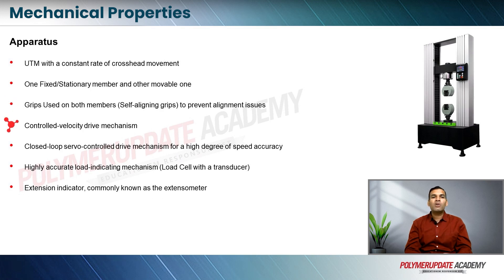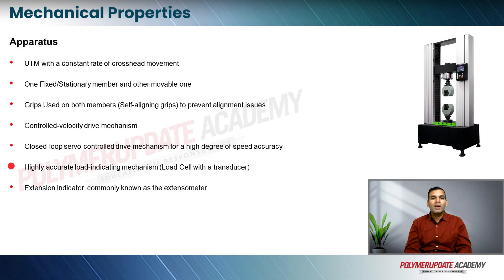There has to be a controlled velocity drive mechanism to move it up and down at a controlled rate of strain. There has to be a closed-loop servo control drive mechanism for a high degree of speed accuracy, which is very important. There also has to be a highly accurate load-indicating mechanism.